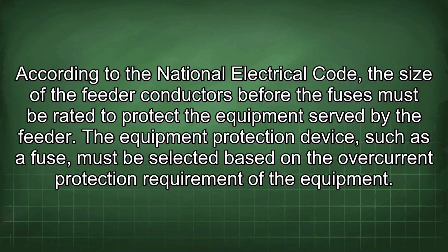According to the National Electrical Code, the size of the feeder conductors before the fuses must be rated to protect the equipment served by the feeder. The equipment protection device, such as a fuse, must be selected based on the overcurrent protection requirement of the equipment.